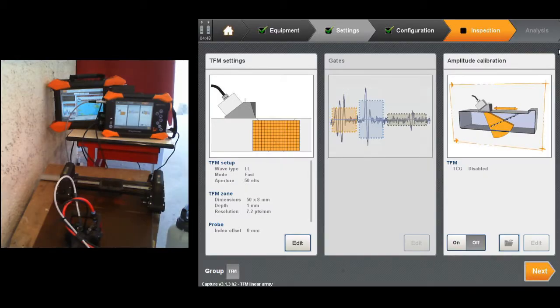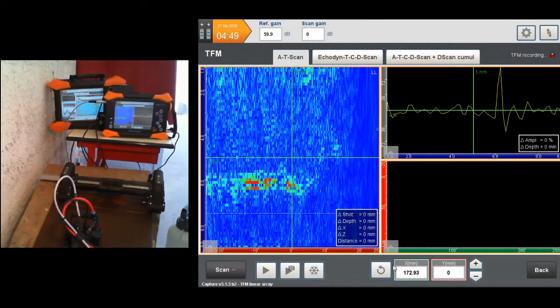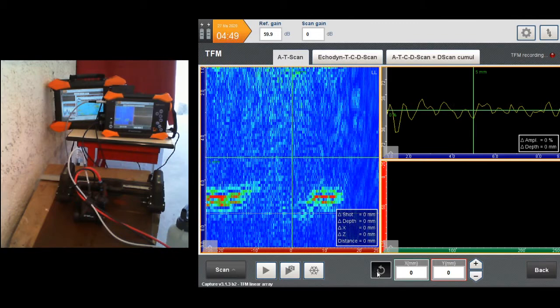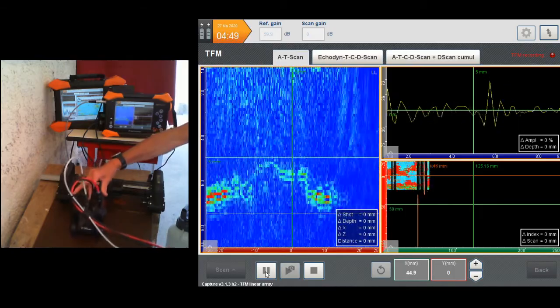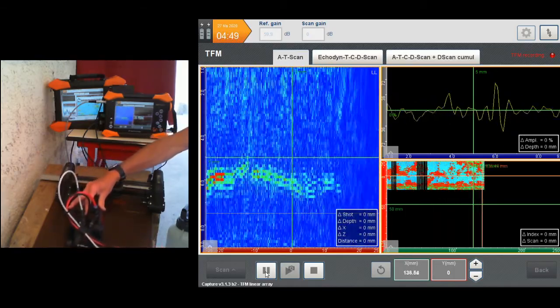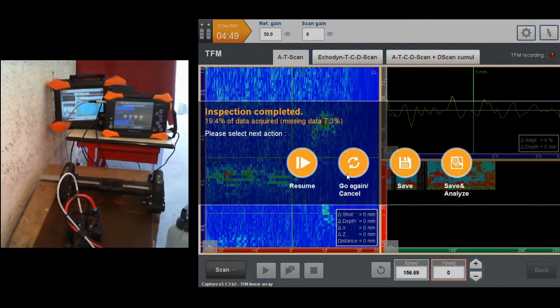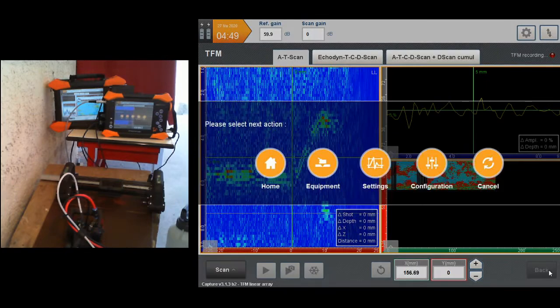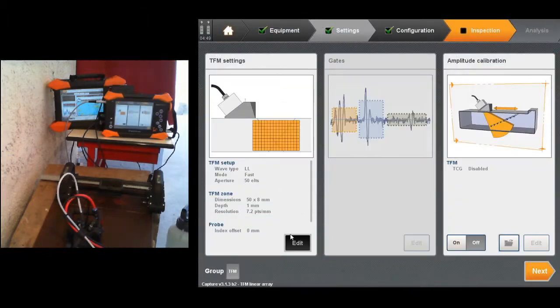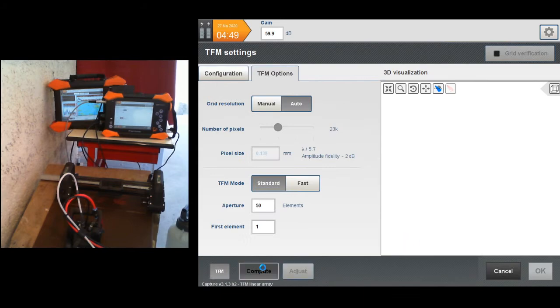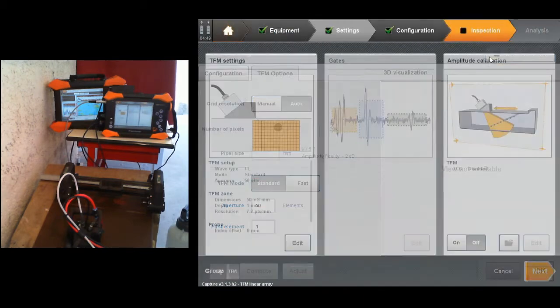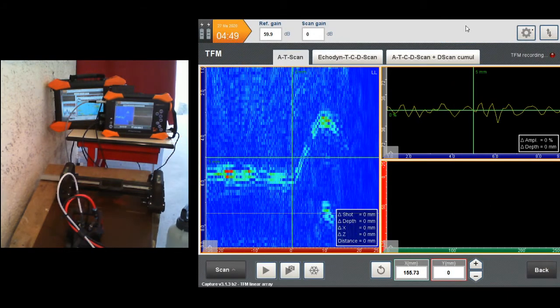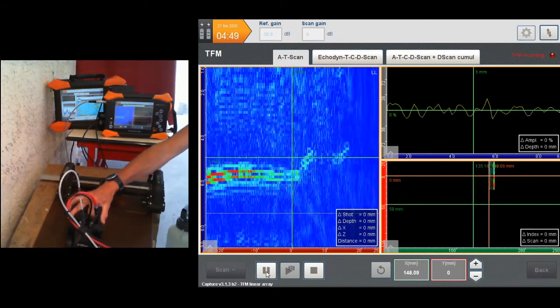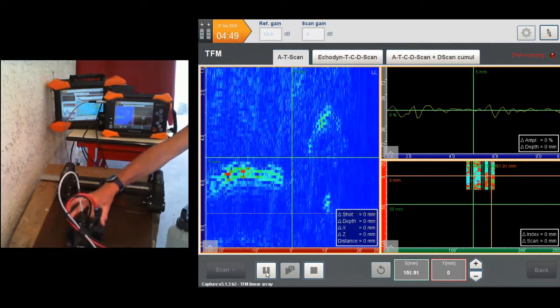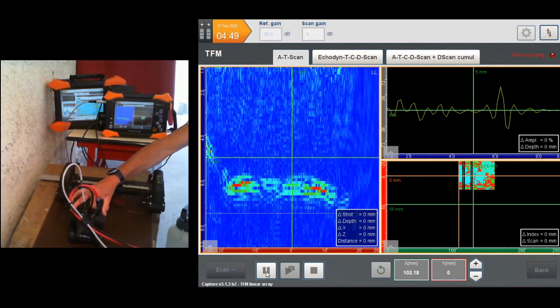Okay, so I was doing, in fact, a scan. I can do it quickly. Okay, going back. You see it's live. Reset, scan, and then I can scan. So if I go too fast, of course, I lose some data. And here it's with a fast mode, which does not give the best results. But if I go to settings and use the best standard FMC TFM, then I know I will have something much nicer. It will be really nicer for sure, but I must scan very, very slowly. If I go too fast, then I miss some data.